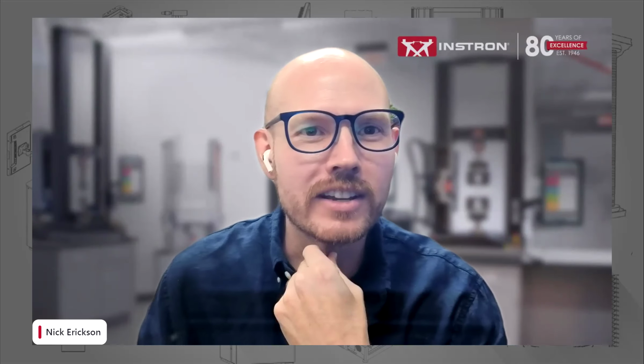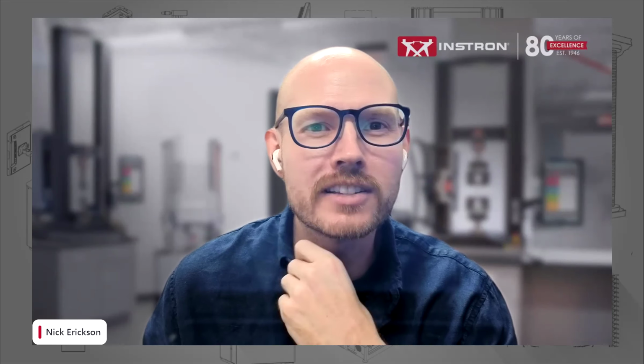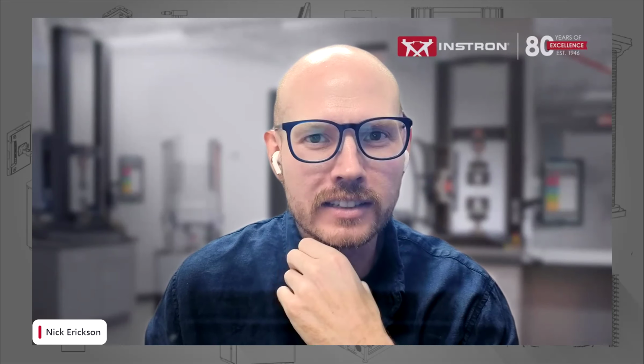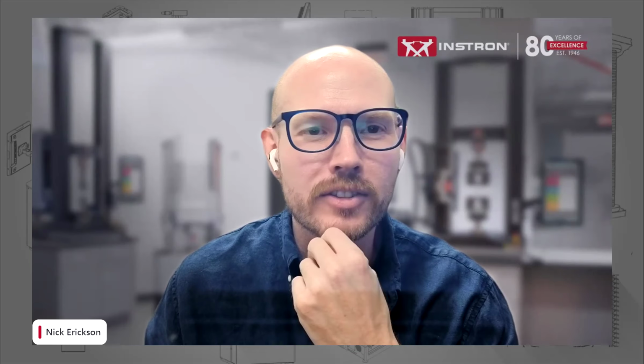Next question we have here is, could you let us know how to recommission our contacting and optical extensometers on our 34TM30 tensile tester? Okay, so it really depends on what extensometers you have. Definitely reach out after this, let us know what you have so we can give you a more tailored response. In general, our teams will check things like what connector type those contacting extensometers have? Clip-ons typically share the same connector and should be compatible with your newer system.